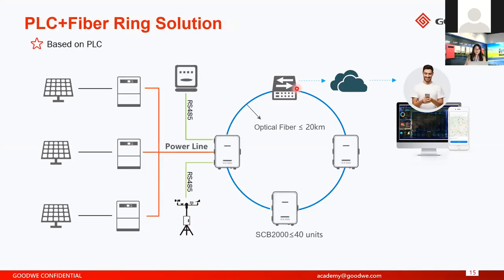And then PLC can have a very similar solution. So as you can see, the inverter connects to the SCB2000 through power line, and there are several SCB2000 boxes, and they all will form a ring. If one link is broken, the data can be transmitted through another link. And also you can connect other devices besides the inverters, like weather station sensors through RS-485 cables.